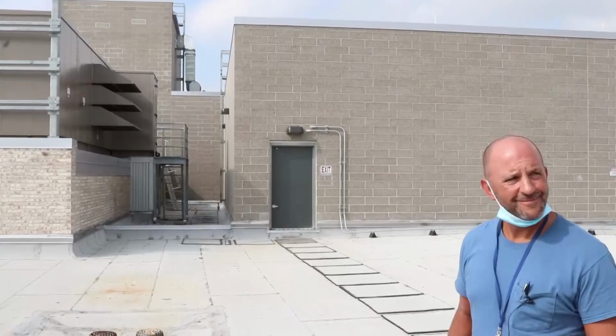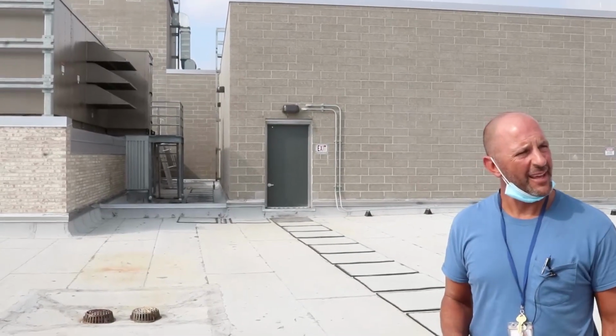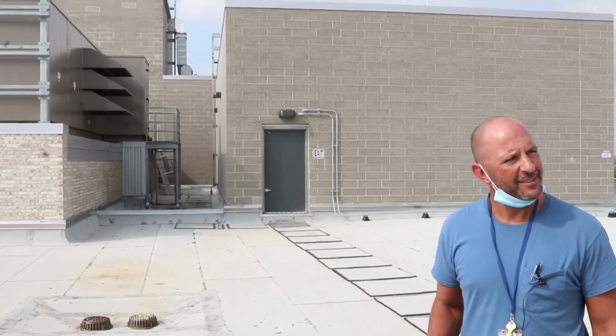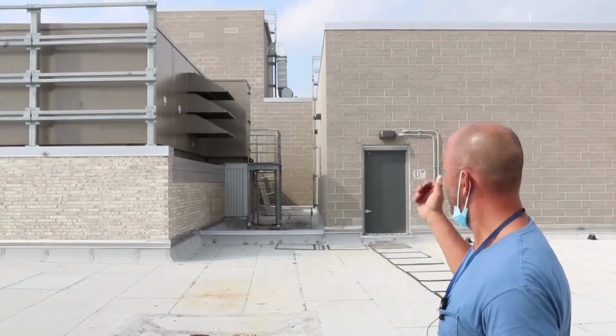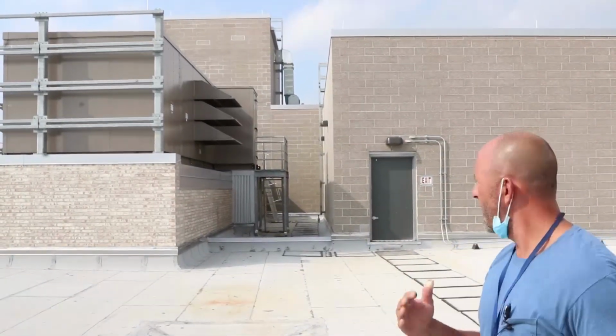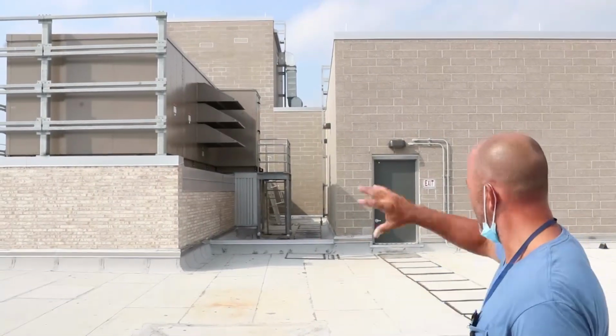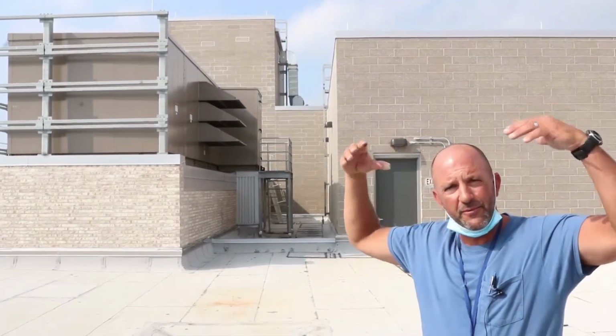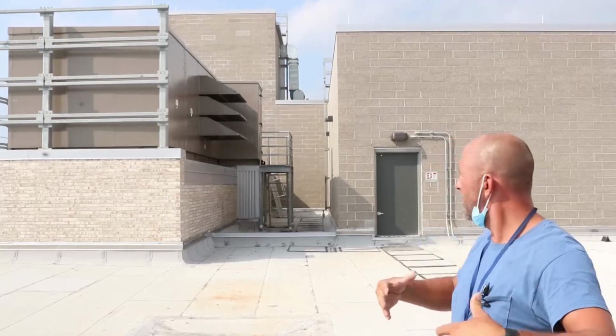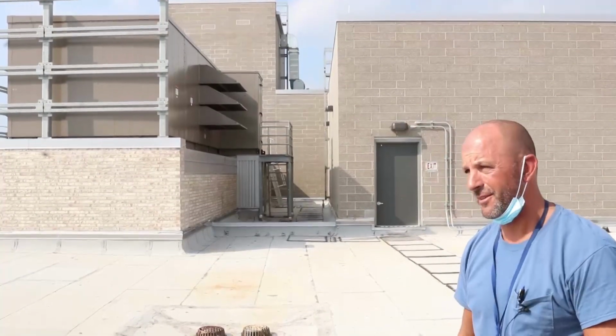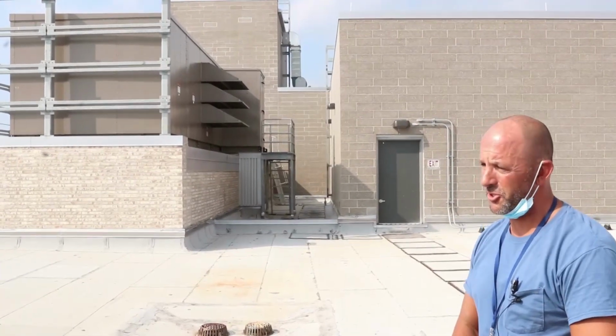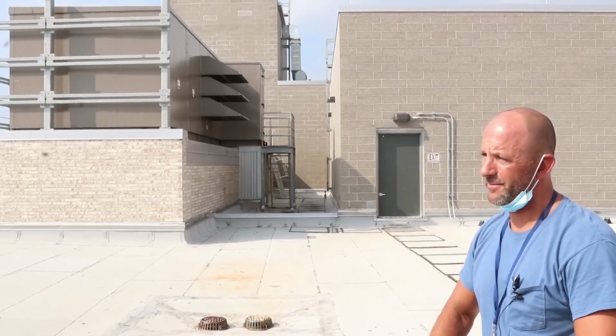Elevator fans he's talking about, is that keyed or does it just go on automatically? No, it goes on automatic. So in a fire condition, that fan starts and pressurizes the room. The fan on the ground, which we'll walk by, is a lot larger because it's pressurizing 5 or 6 stories of the shaft, maybe more, all the way down. It just keeps smoke out of the elevator.